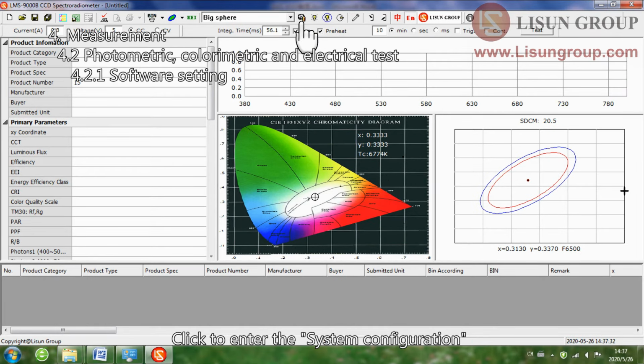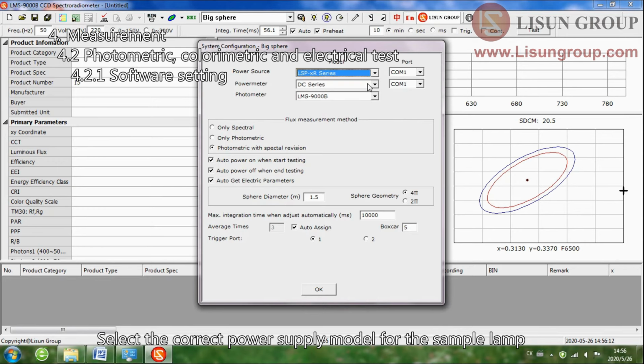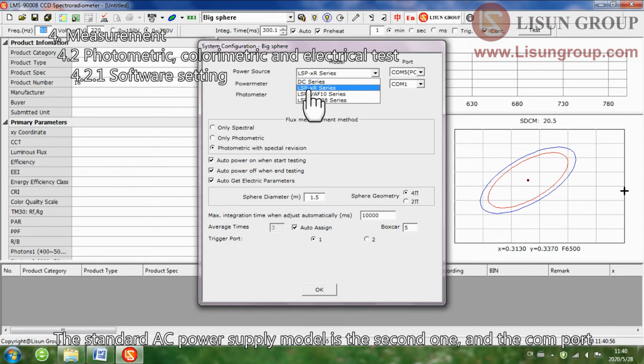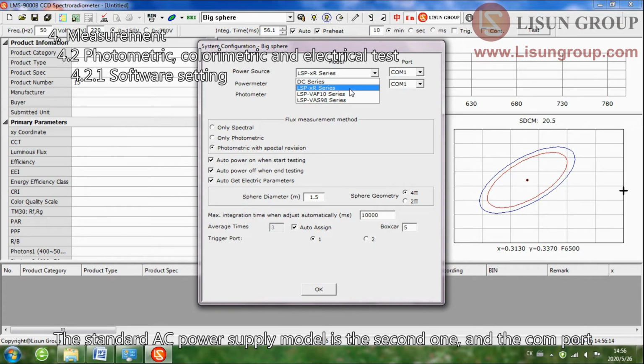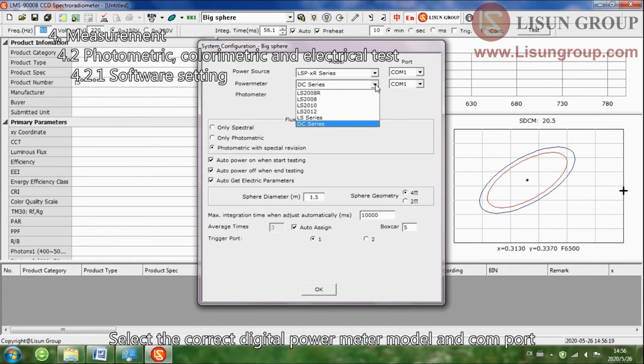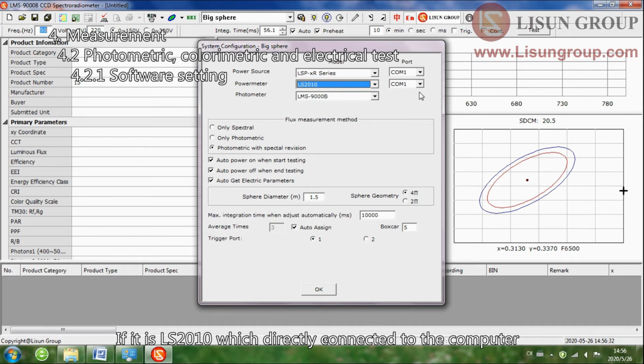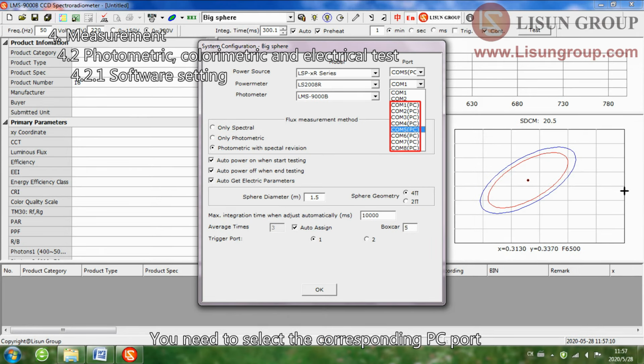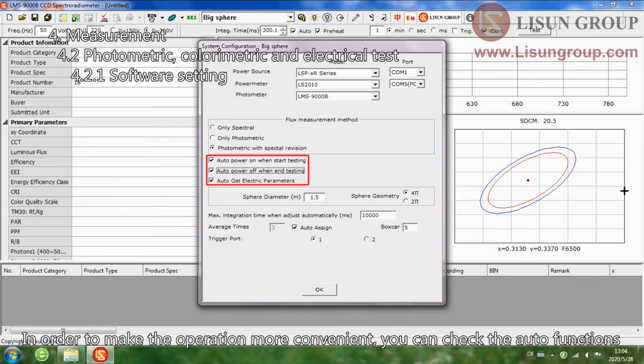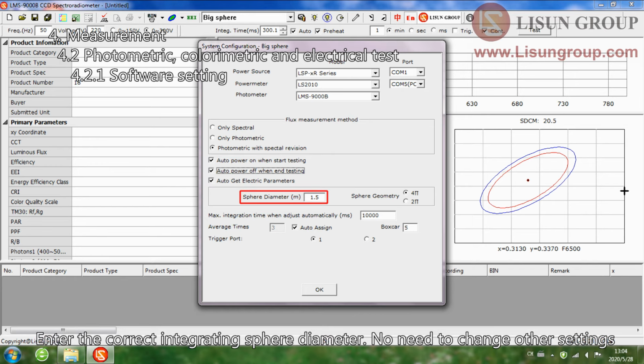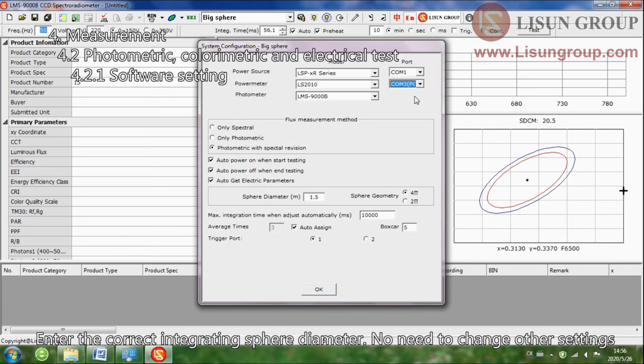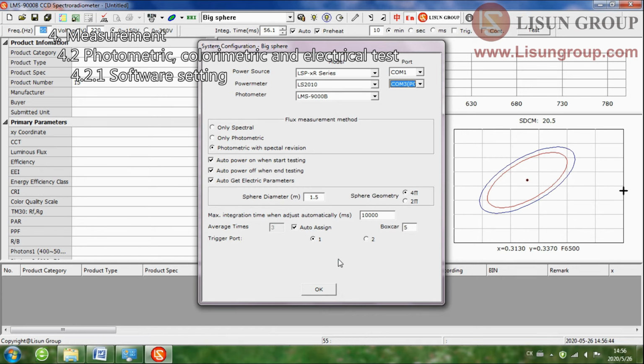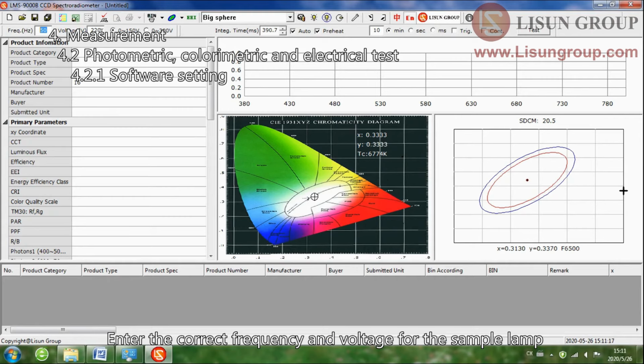Click to enter the system configuration. Select the correct power supply model for the sample lamp. The standard AC power supply model is the second one, and the COM port. Select the correct digital power meter model and COM port. If it is LS2010 which is directly connected to the computer, you need to select the corresponding PC port. In order to make the operation more convenient, you can check the auto functions. Enter the correct integrating sphere diameter. No need to change other settings. Enter the correct frequency and voltage for the sample lamp.